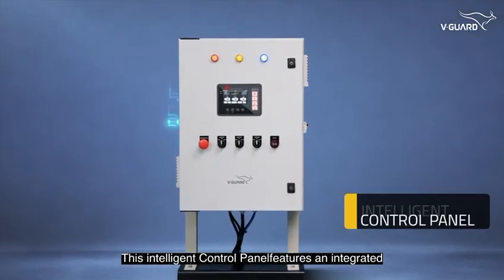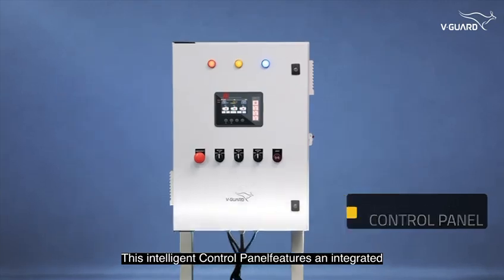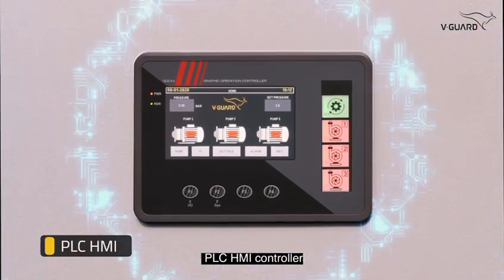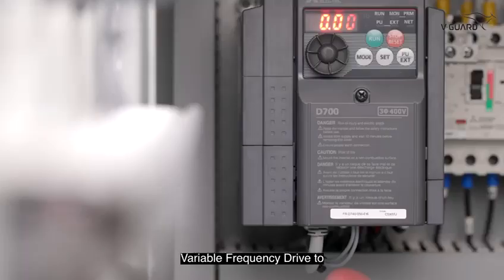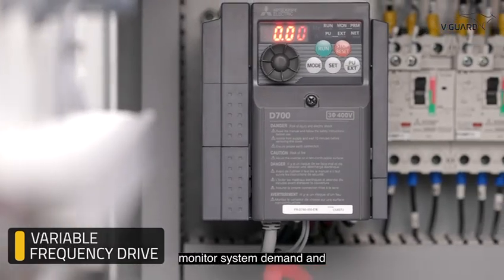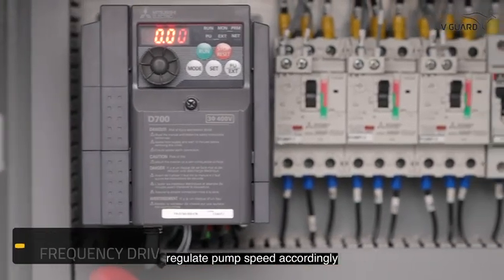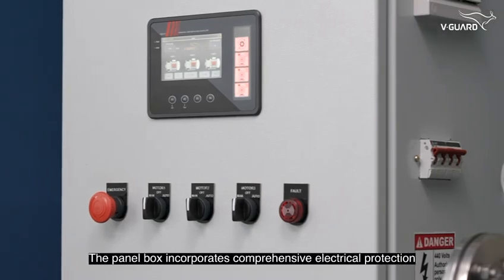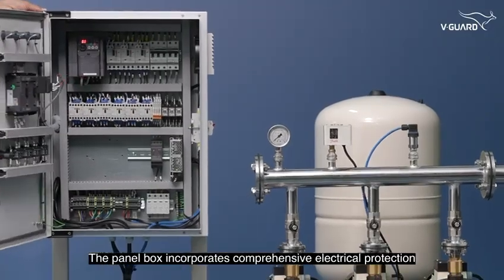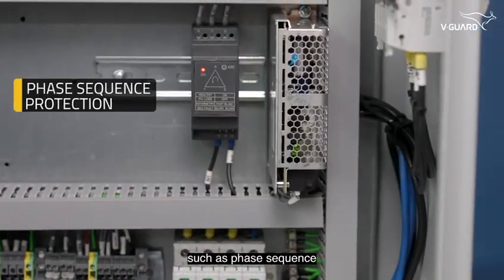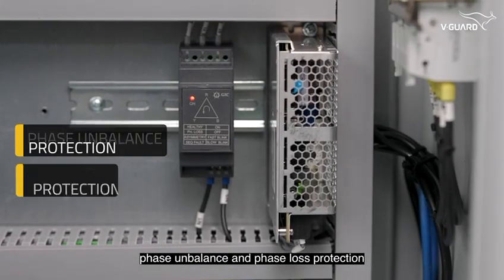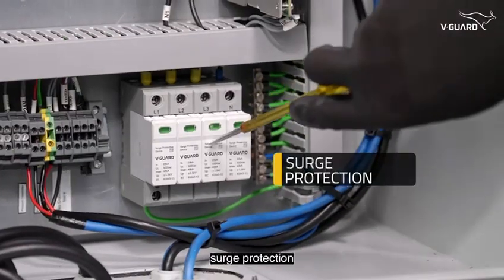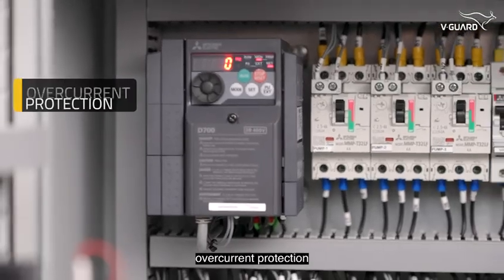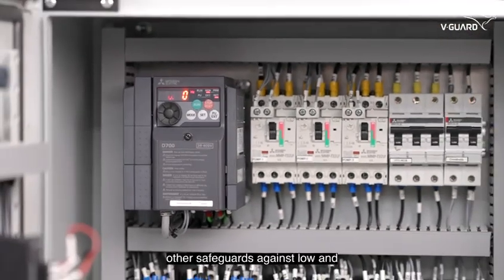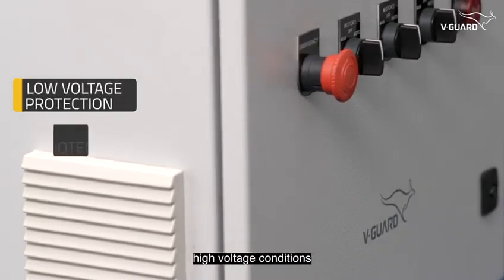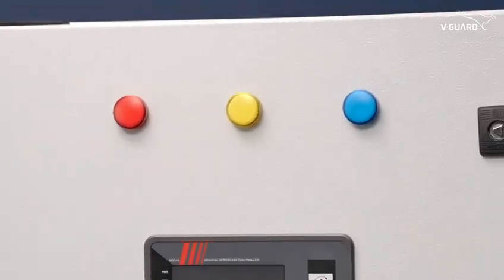This intelligent control panel features an integrated PLC-HMI controller that works alongside a variable frequency drive to monitor system demand and regulate pump speed accordingly. The panel box incorporates comprehensive electrical protection such as phase sequence, phase unbalance, and phase loss protection, surge protection, overcurrent protection, dry run protection, and other safeguards against low and high voltage conditions.